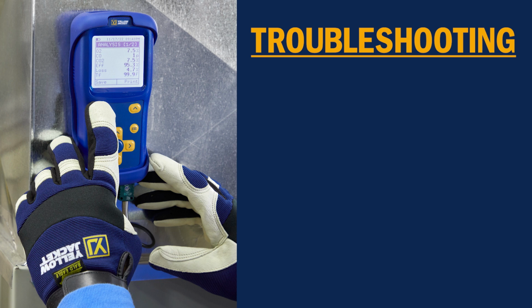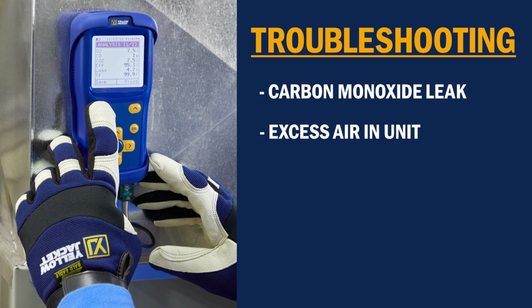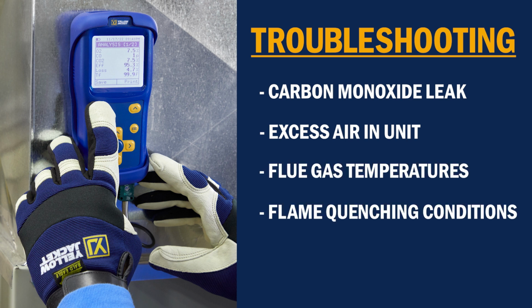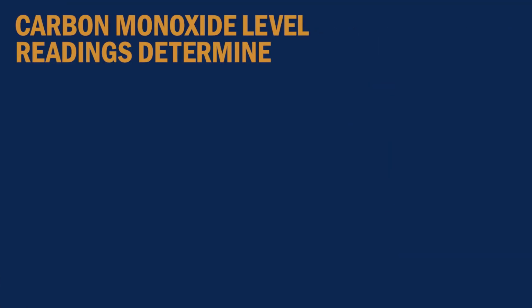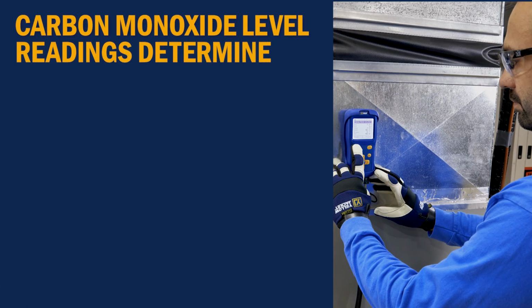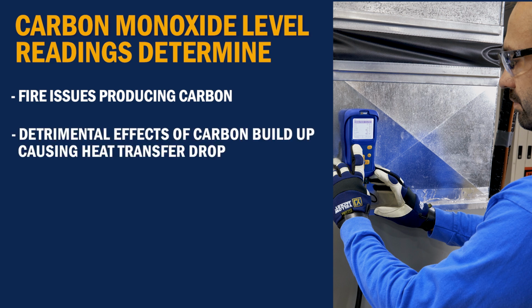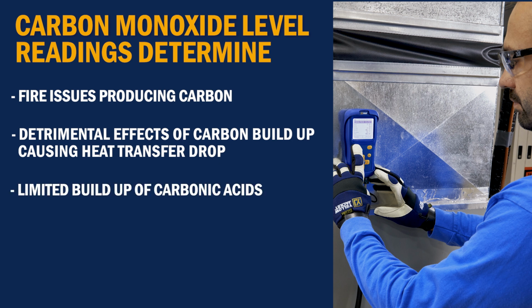The Combustion Analyzer is more than just a way to test for a CO leak in your heating system. While it tells you the CO it is seeing, it also tells you important troubleshooting things like how much excess air the unit has, the flue gas temperatures, as well as any flame quenching conditions and the overall furnace condition. The ability to read the carbon monoxide levels helps you determine fire issues producing carbon and the detrimental effects of the carbon as it builds up and becomes an insulator and causes overall heat transfer to drop in the system, as well as limiting your buildup of carbonic acids.